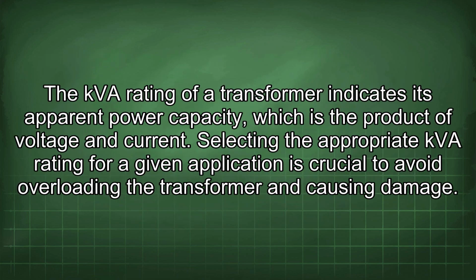The kVA rating of a transformer indicates its apparent power capacity, which is the product of voltage and current. Selecting the appropriate kVA rating for a given application is crucial to avoid overloading the transformer and causing damage.